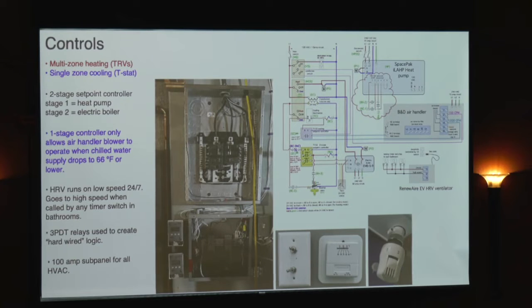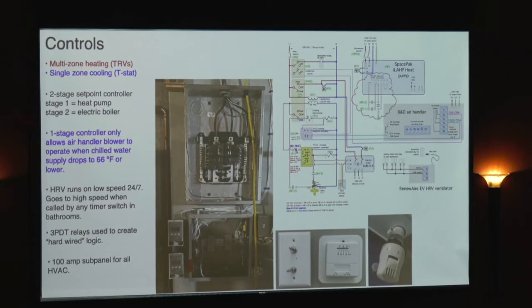So if we switch from cooling and go immediately to heating, the chilled fluid that's in the piping between the heat pump and the mechanical space is going to get injected into that buffer tank. Now, you may never detect that, but in the opposite direction, let's say you've been heating the buffer tank, it's a hot day in July, you've temporarily shut off the blower in the air handler, and now you come back out of heating and go into cooling, you're going to send 110, 120 degree fluid through the coil in the air handler. Granted, that's only going to last 2 or 3 minutes, but the last thing that an occupant wants to feel on a hot day when the cooling system's going is a burst of warm air coming out of the registers.